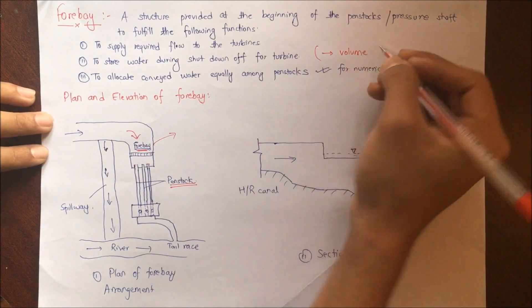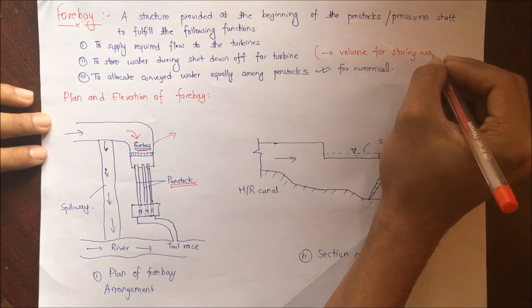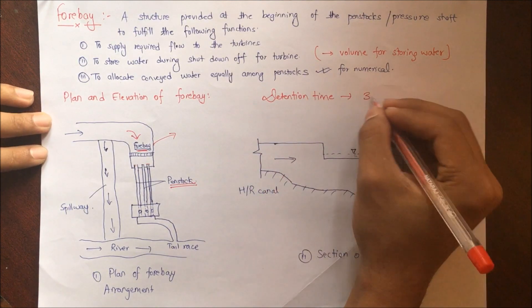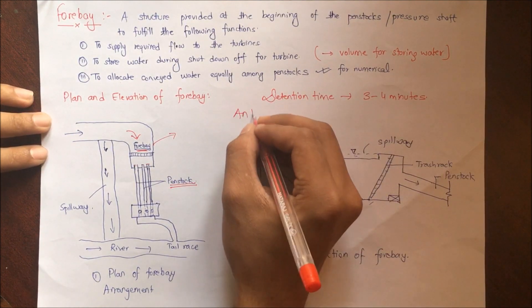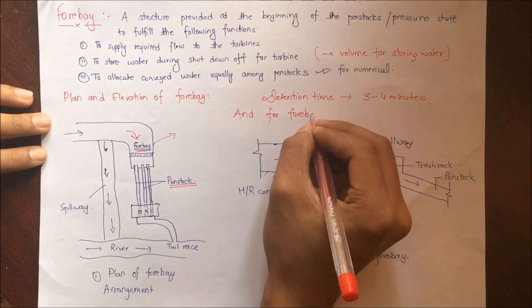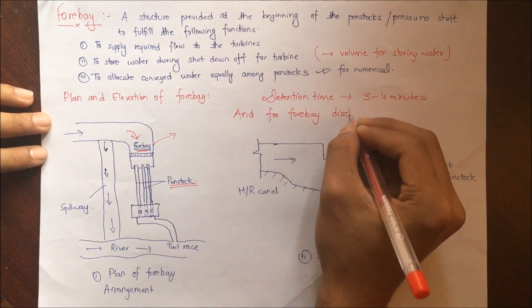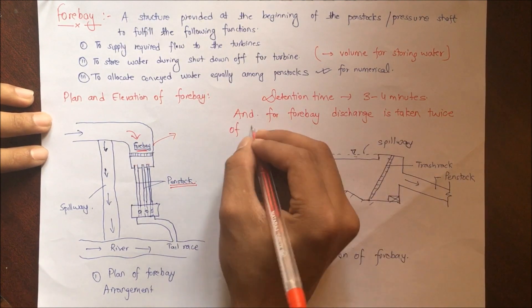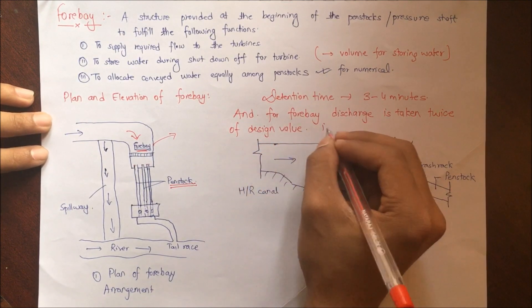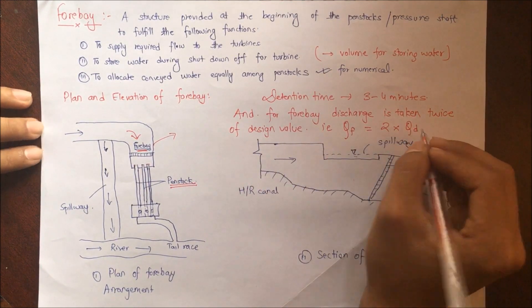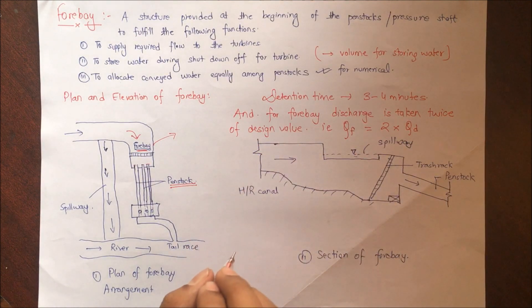Now we are interested in the design of forbay, so we have to consider the volume for storing water. Before that we have to consider the detention time. As I said, during the shutdown of turbine, water has to be stored in forbay. Volume for storing water and the detention time is the time for which the turbine will be shut down. For forbay, discharge is taken twice the design value. Water has to be stored, so the design discharge or the discharge for forbay is taken as twice of design discharge.